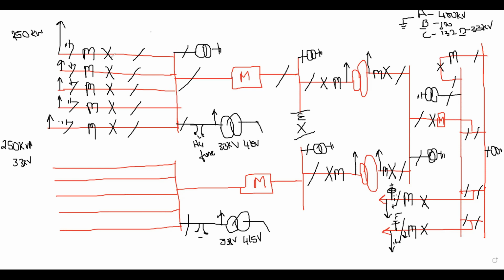And wherever a breaker is there, I will consider this as one feeder. A breaker, we will call a feeder or a bay. Wherever there is a breaker, we will call that a bay or a feeder. So in the 33 kV, how many bays are there? 1, 2, 3, 4, 5, 6, 7, 8, 9, 10. And this is not a bay because there is no breaker. 10, 11, 12, 13. So 13 feeders are there in my 33 kV. And in 220 kV, 1, 2, 3, 4, 5, 6. 6 bays in the 220 kV. A bay or feeder represents a breaker, CT, everything.